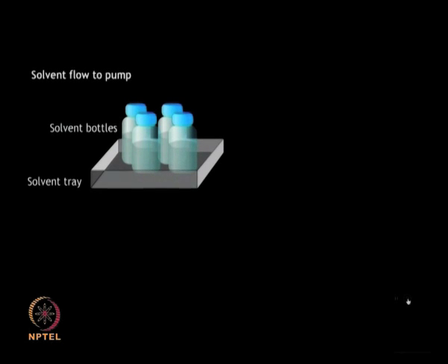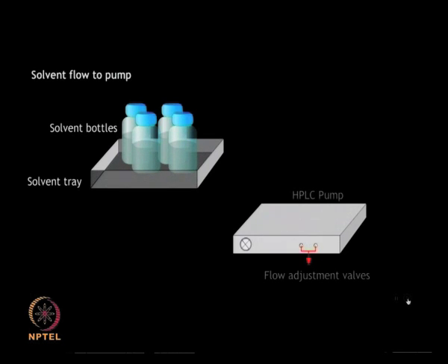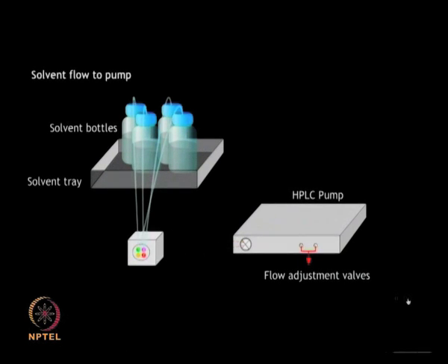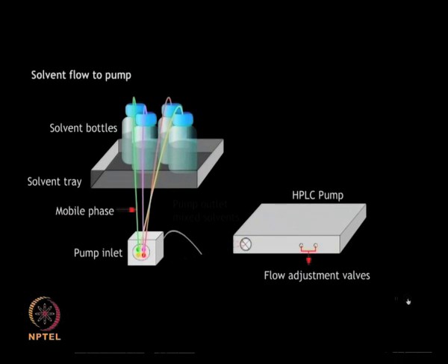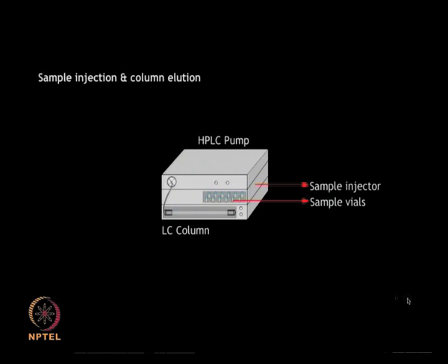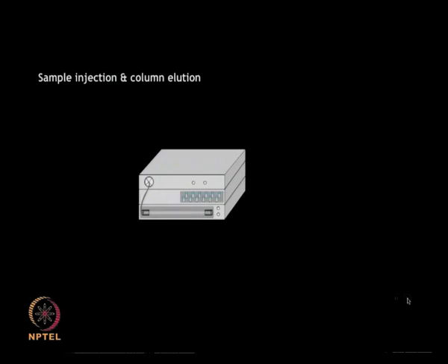A typical liquid chromatography setup consists of solvent bottles, degasifier, dual or binary pumps, sample injector, column, and detectors. Here you can see the various components involved in performing liquid chromatography. Different solvents can be placed in the solvent bottles depending upon the purification requirements. The solvents are mixed in the desired ratio and pumped into the column during elution, after removal of any trapped air by means of the degasifier.